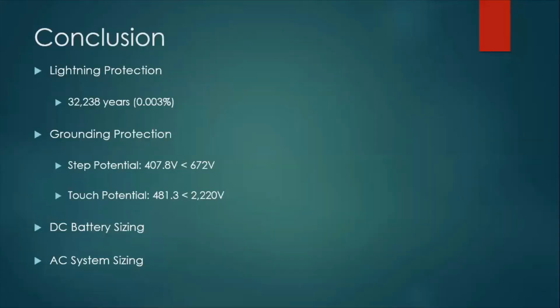In conclusion, the lightning protection was designed to IEEE standards and exceeded the goal of allowable strokes. The grounding study had both touch and step potentials below the maximum allowable voltage. The DC batteries are able to operate for the minimum 8 hours, and all AC substation loads can be serviced at any time of the year.